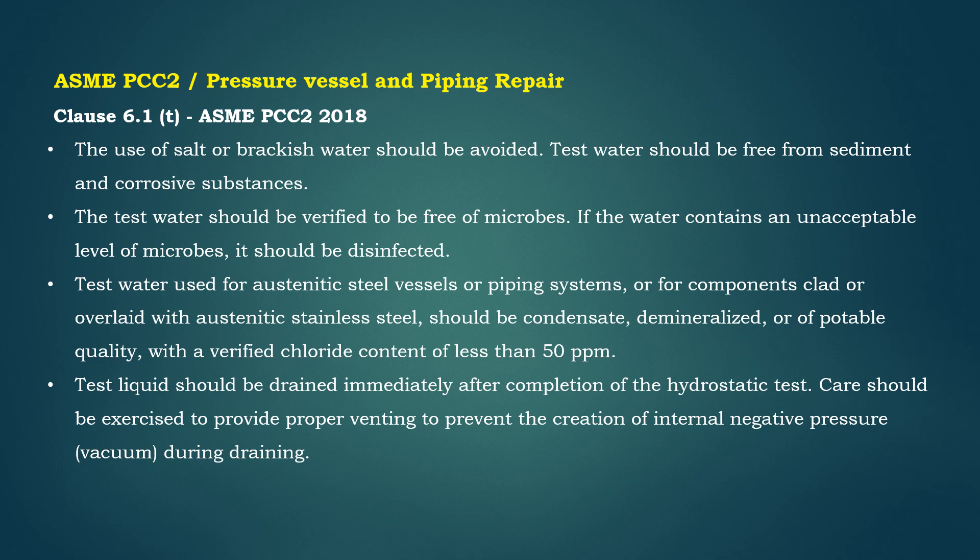Test water used for austenitic steel vessels or piping systems, or for components clad or overlaid with austenitic stainless steel, should be condensate, demineralized, or of potable quality with a verified chloride content of less than 50 ppm. Test liquid should be drained immediately after completion of the hydrostatic test. Care should be exercised to provide proper venting to prevent the creation of internal negative pressure or vacuum during draining.